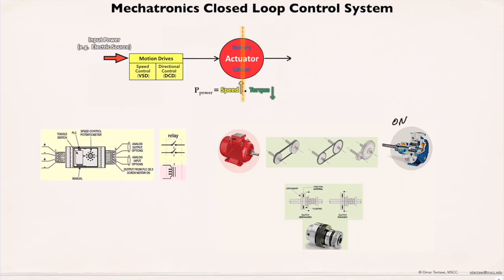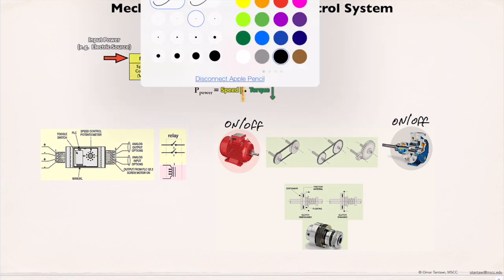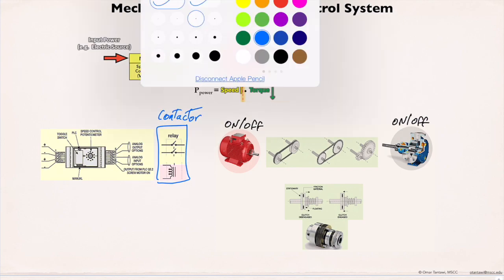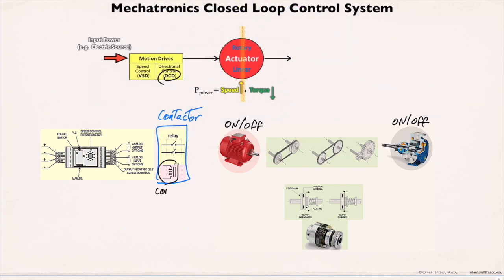Switching the pump on or off is done by switching the motor on or off, which is done by a motion drive called a direction control drive, or contactor. Switching the motor is controlled electrically using a coil attached on the contactor as one built-in device. When the contactor coil receives a signal from the system controller, the contactor contacts close and supply the motor with energy. If the control signal is disconnected, the contacts open mechanically by a spring, disconnecting the motor from the source.